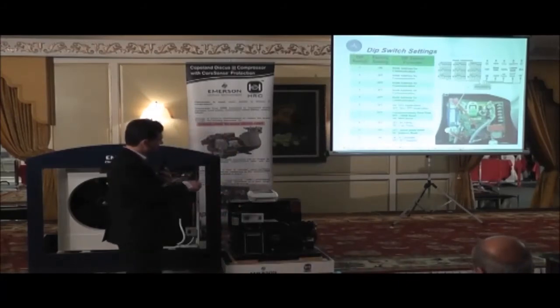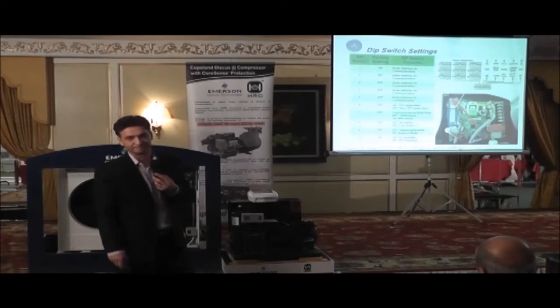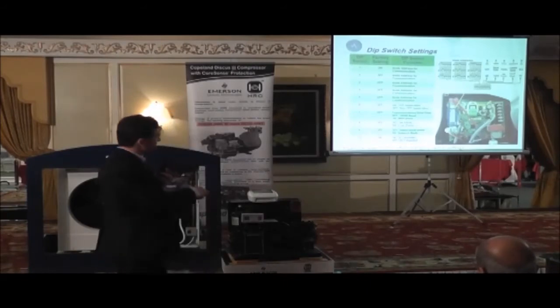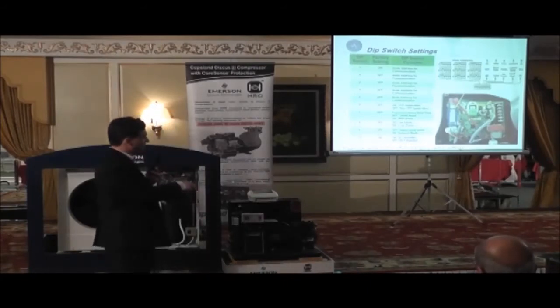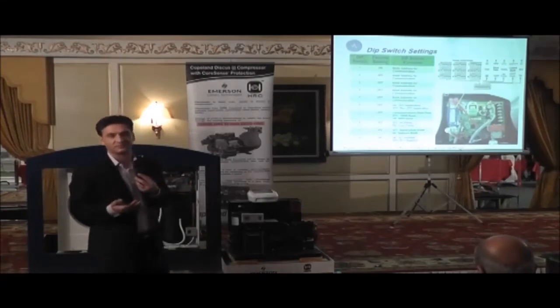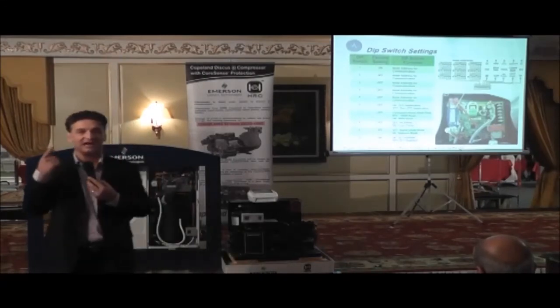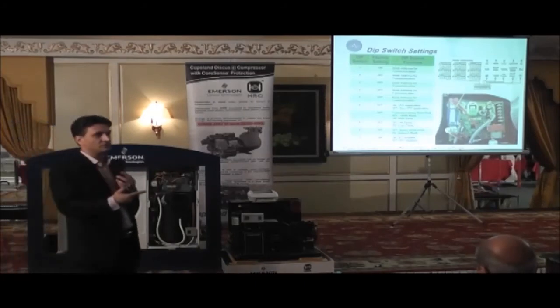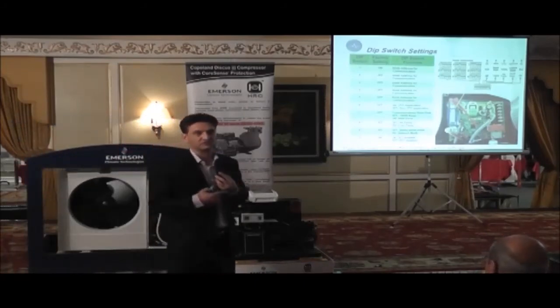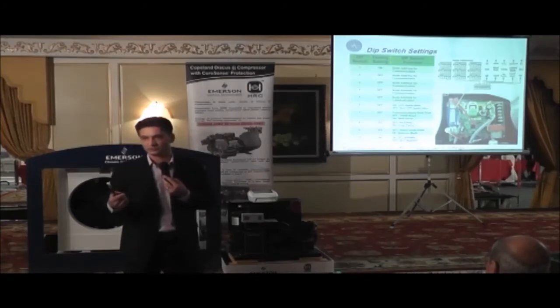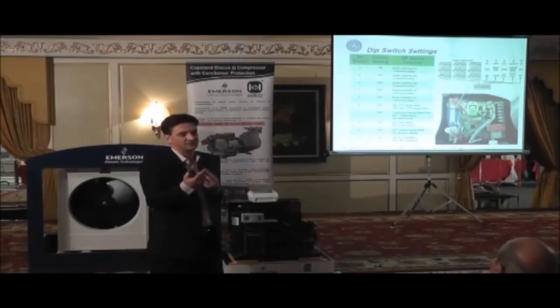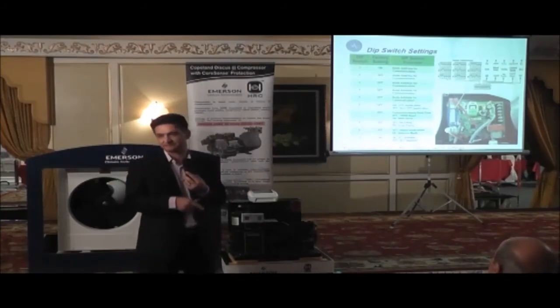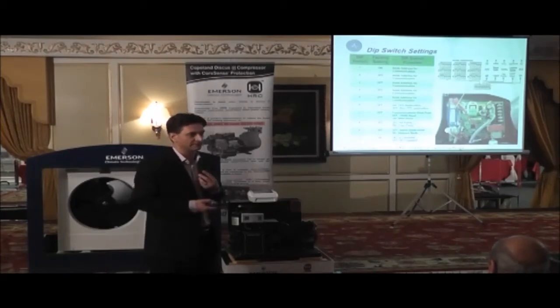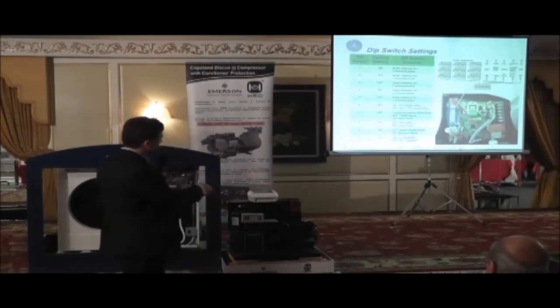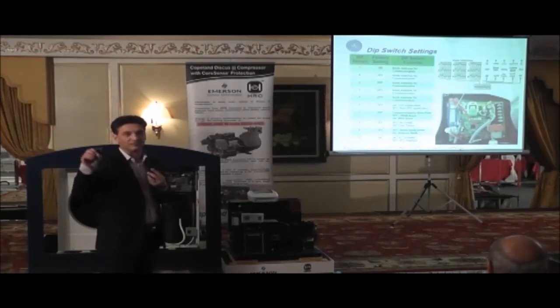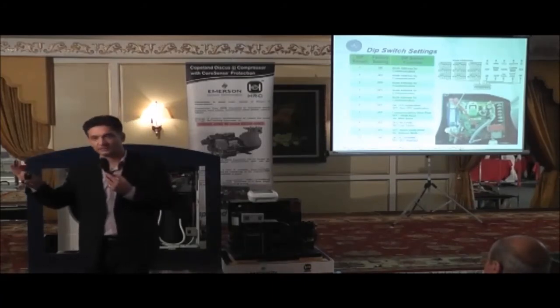Number 10, discharge temperature. Okay. When you receive the compressor, this will be switched to on because we are trying to protect the compressor from overheating. However, if you're using this compressor with demand cooling, which is still going to be required for R22, or if the refrigerants transition to 407A, you still need to use demand cooling. In this case, we're going to switch it off, and we're going to allow the demand cooling to become the master.